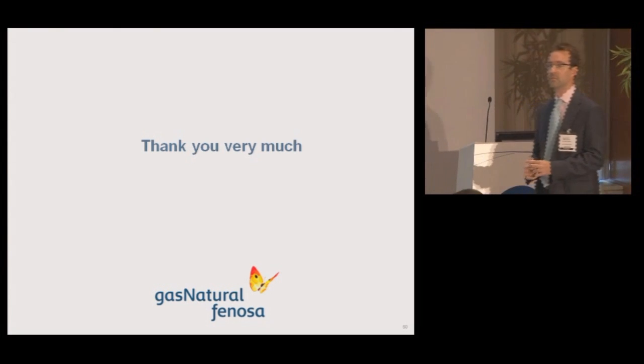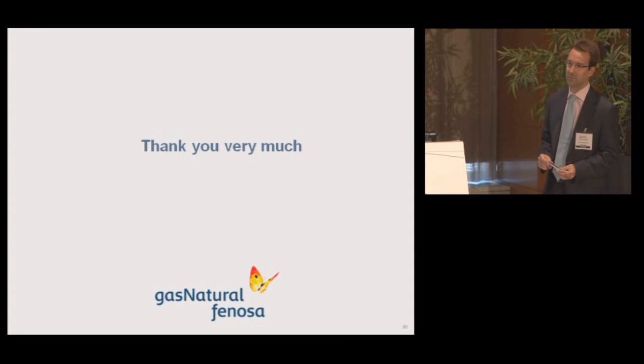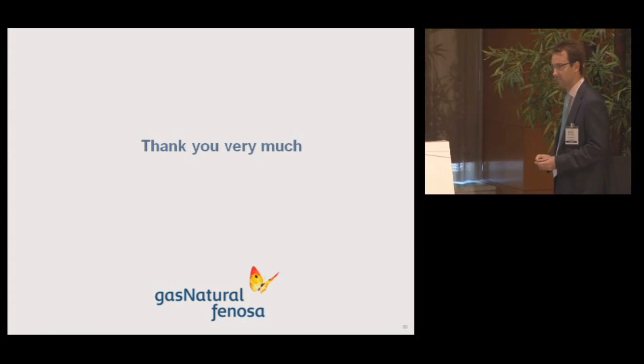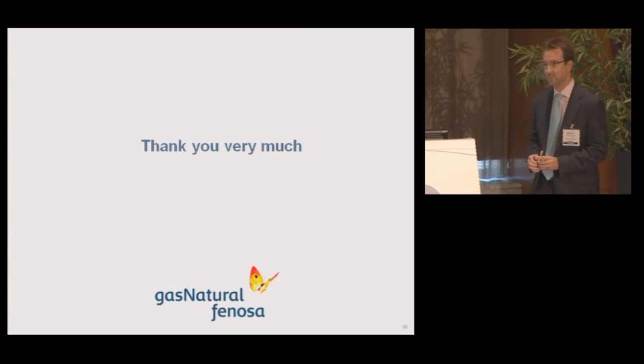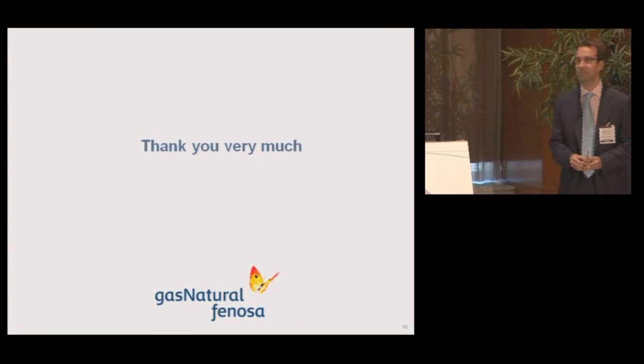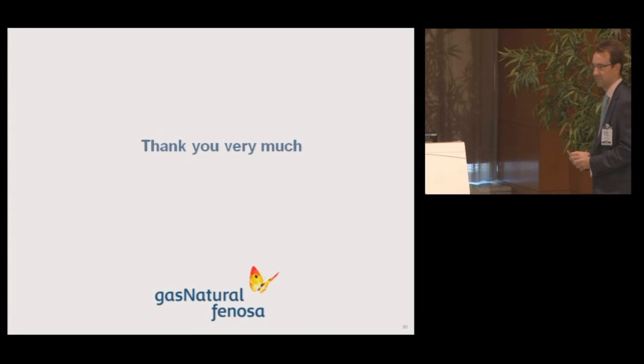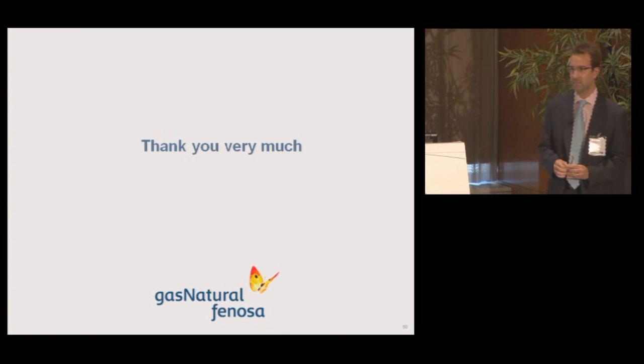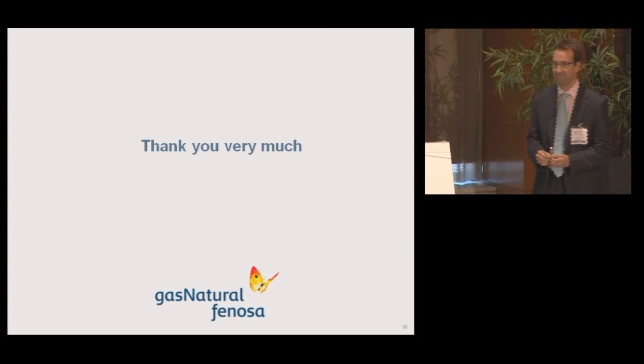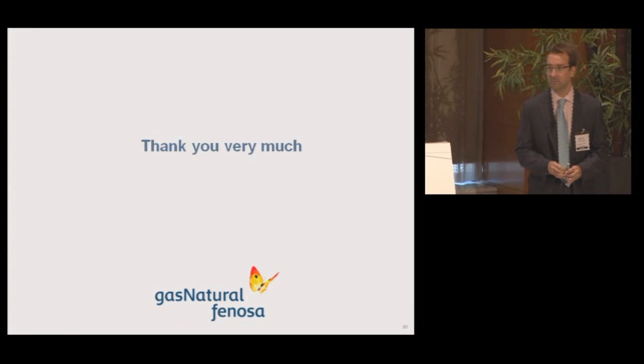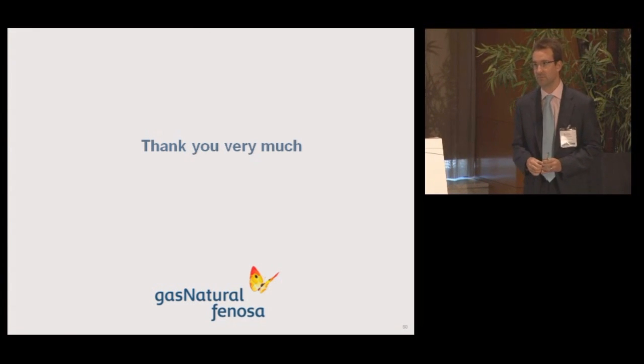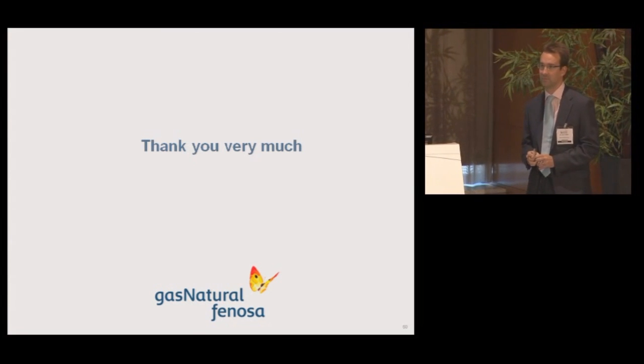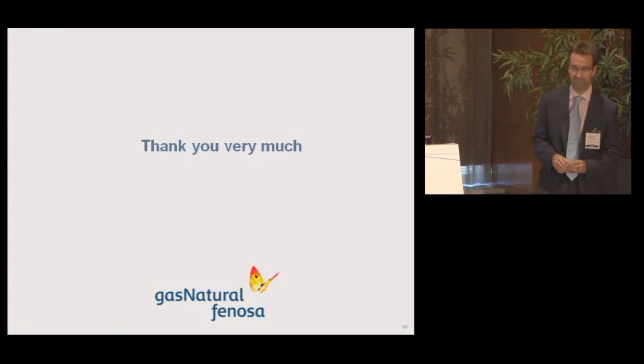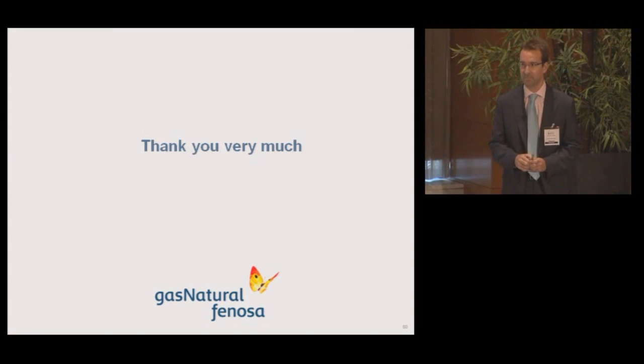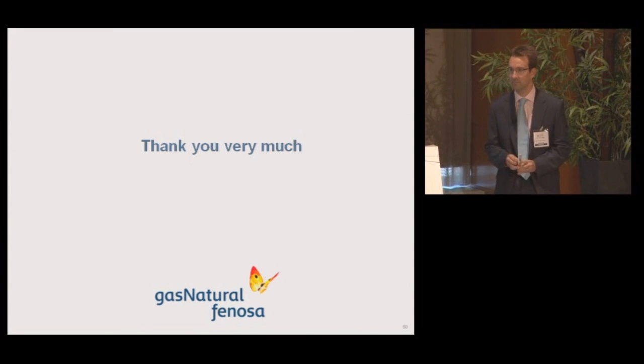Antonio Gomez, University of Seville. I think this is a very important presentation that complements the vision we got yesterday. Somebody told us yesterday that the smart grids issue is mostly related to information technology, but now we've seen clearly here that it's also related to grids themselves. Before being smart, they are grids, and this has constraints and limitations that we should take into account, otherwise we don't have energy flow at all. So this is important and should be taken into account. In particular, the overvoltage problem in the presence of distributed generation is a very important issue. So the conclusion that keeping power factor constant is by no means acceptable nowadays, considering the capabilities of power converters that are able to control active and reactive power independently. So this is just a comment, not a question, just to elaborate.